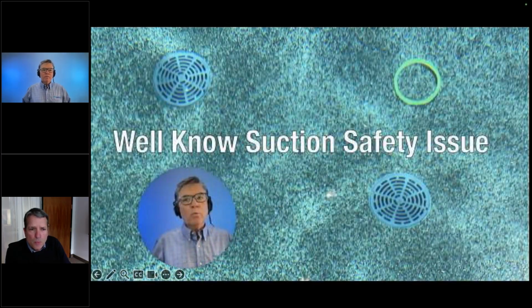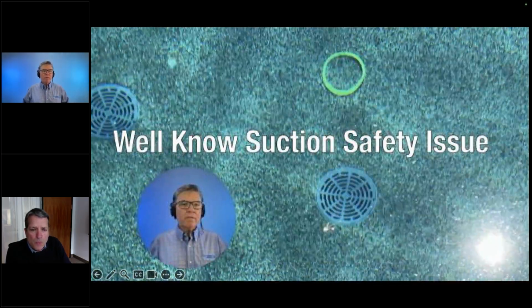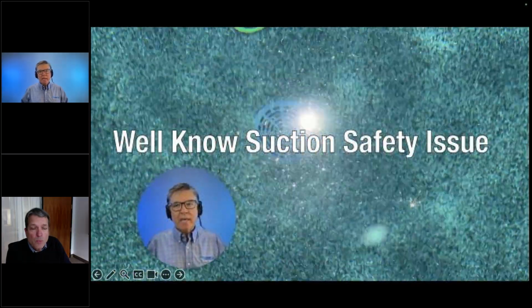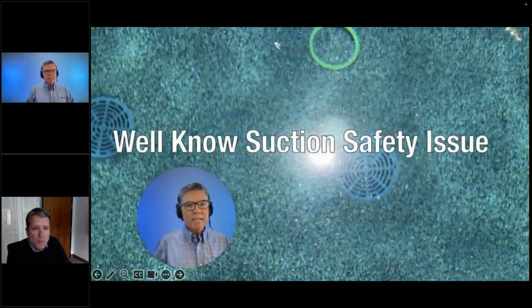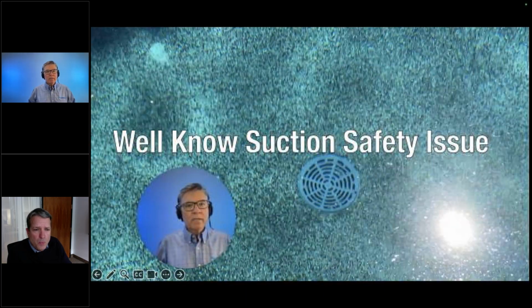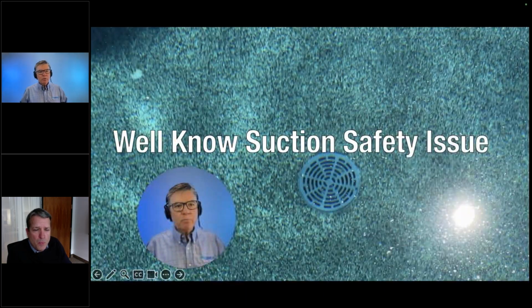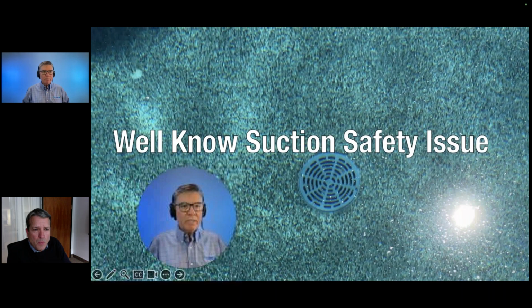So pay attention to the drain covers, keeping in mind that these hazards are normally invisible and potentially deadly when you put in a variable speed pump, and this is what you find in the pool. These flat and flush mount drains have been illegal since 2007, but have continued to be sold on that big smiley company that sells anything and everything and will deliver on a Sunday night. And they've had to pull down flat and flush mount drains like this just this year. There was a recall on this style that was being sold through that online retailer. So please be careful and be aware.